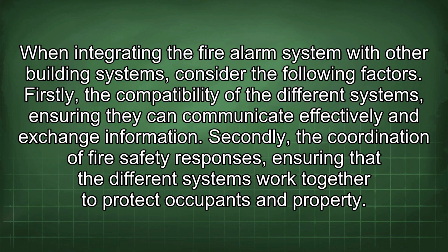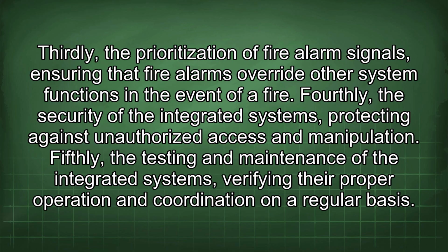When integrating the fire alarm system with other building systems, consider the following factors. Firstly, the compatibility of the different systems, ensuring they can communicate effectively and exchange information. Secondly, the coordination of fire safety responses, ensuring that the different systems work together to protect occupants and property. Thirdly, the prioritization of fire alarm signals, ensuring that fire alarms override other system functions in the event of a fire. Fourthly, the security of the integrated systems, protecting against unauthorized access and manipulation. Fifthly, the testing and maintenance of the integrated systems, verifying their proper operation and coordination on a regular basis.